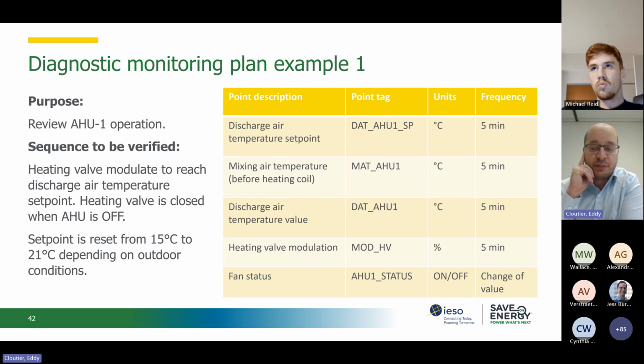So here is the first very simple example of a diagnostic monitoring plan. In this case, we want to validate how an air handling unit operates. More precisely, how it modulates its temperature, validate if the temperature reset sequence is functional, and if the heating valve operates correctly. So here's an example of the list of points that we could follow. You see the discharge air temperature set point, the mixing air temperature in the air handling unit, the discharge air temperature or supply air temperature of the unit, heating valve modulation, fan status. So this is an example only.